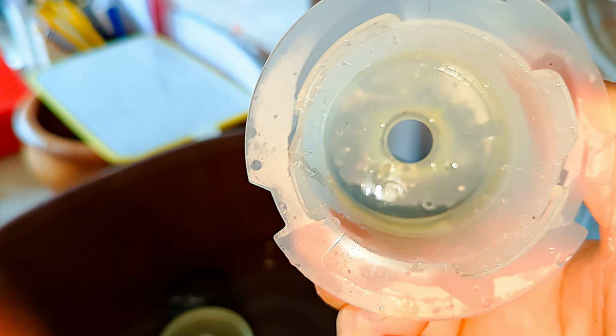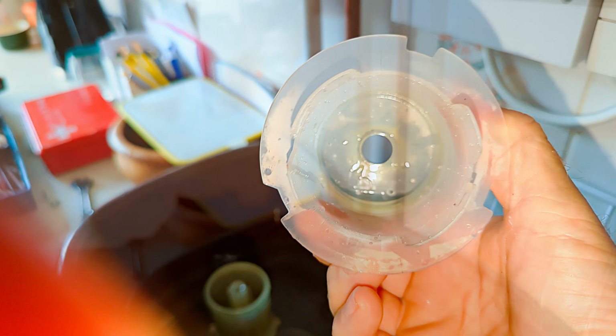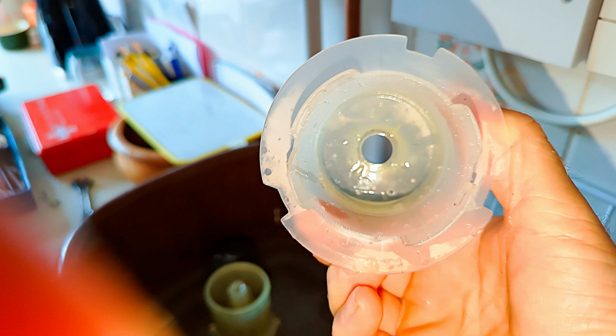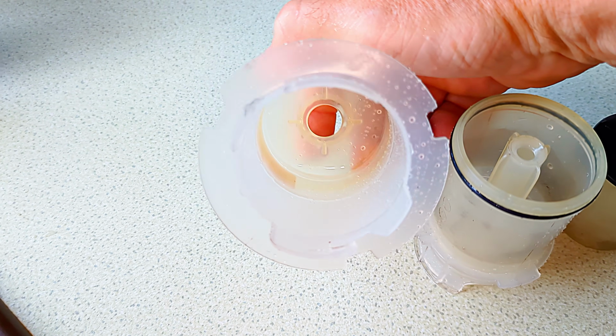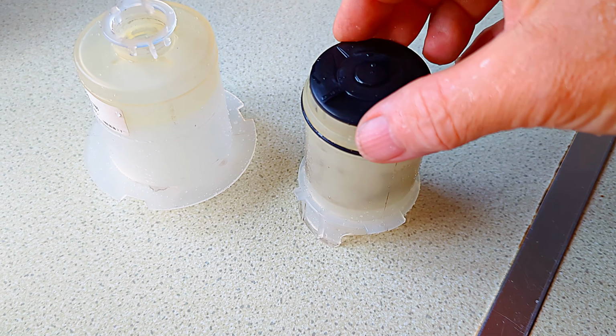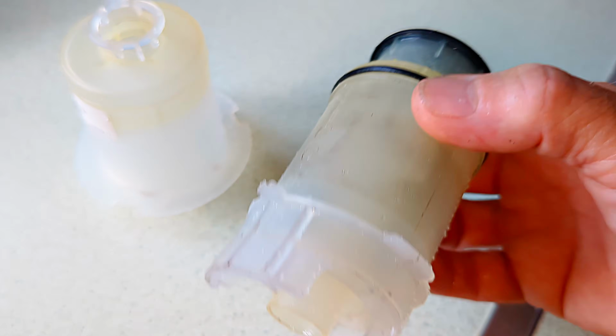So push your skewer up into the hole from the bottom of the boiler and push it into the hole, wiggle it around and make sure there is no blockage or that the blockage is then cleared. And of course, water will then come pouring out of the trap if you did have a blockage. So let's take a quick look at the trap itself. I've cleaned it all up now before I put it back onto the boiler.